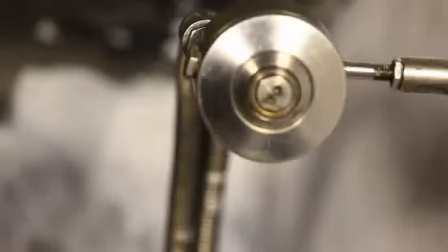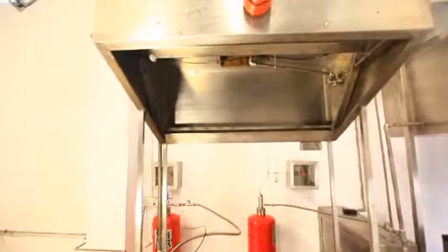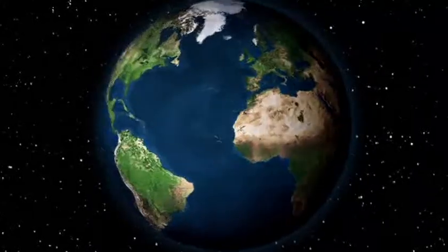Water may be fire's most potent enemy, with its massive cooling power of 2.6 MW per liter per second. But you need a lot of water to put out a fire effectively. Often there's post-fire collateral damage too, because water damages furniture, valuable objects, and electronics like computers. And then there's the added danger of electrocution when trying to battle fires involving electronic devices. The need for today then is cutting-edge technology that changes water's natural form so that water can fight all kinds of fire without causing any collateral damage to the premises or the earth. We call that firefighting technology water mist.